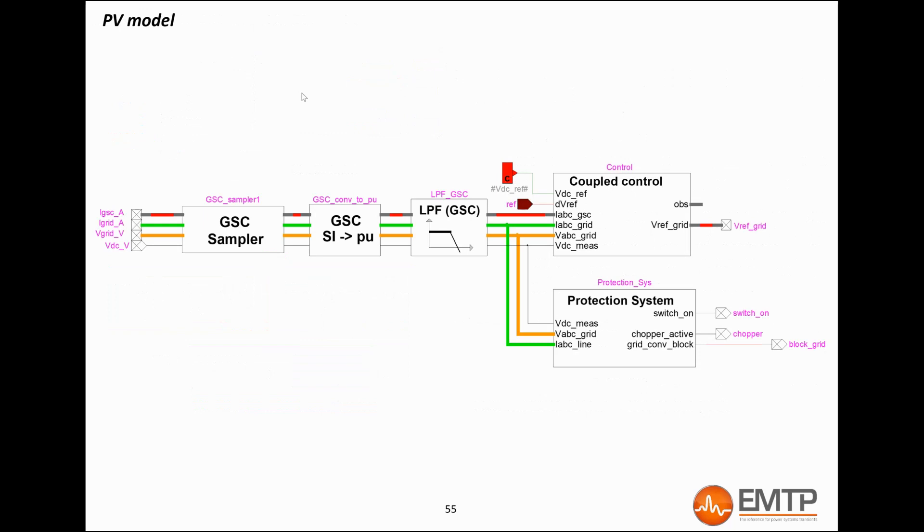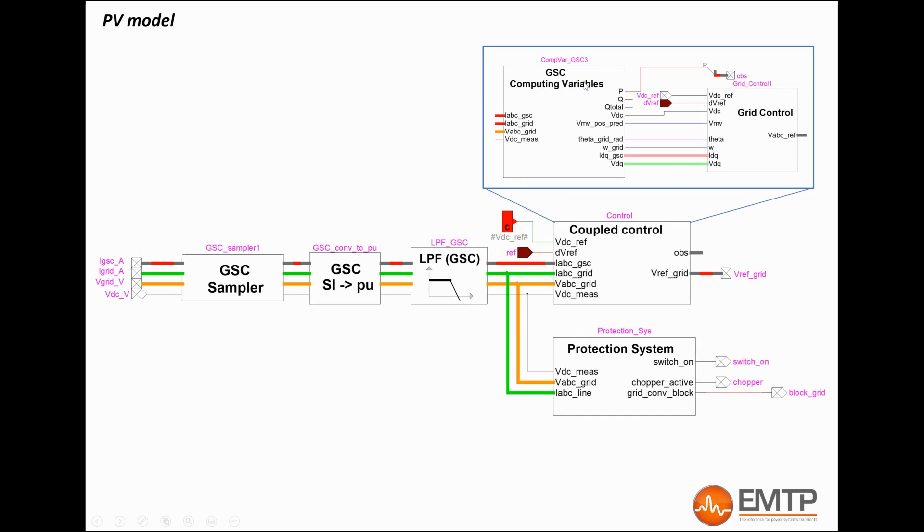Here is the control and protection diagram of the EMTP 4.1 PV park. The sampled signals, which are the voltage and current on each side of the converter, are put in per unit and filtered. The input measuring filters are low-pass type. The compute variables block computes the variables used by the grid control device and the protection system.